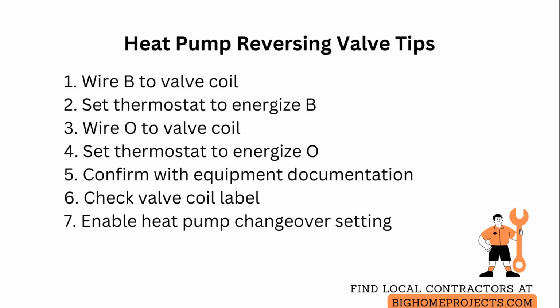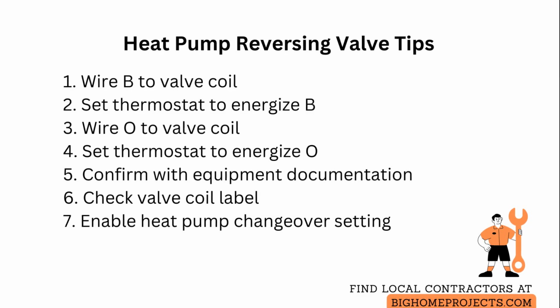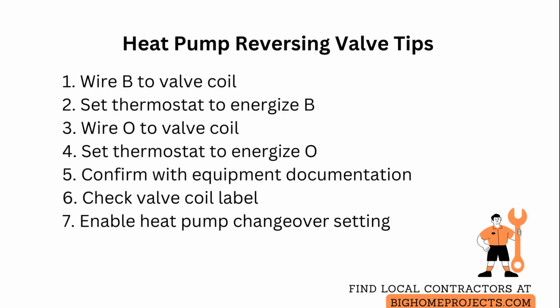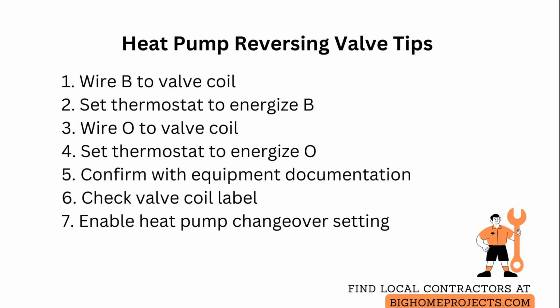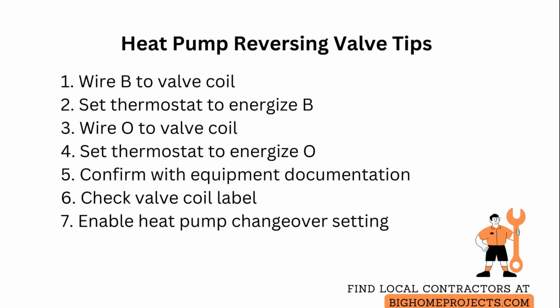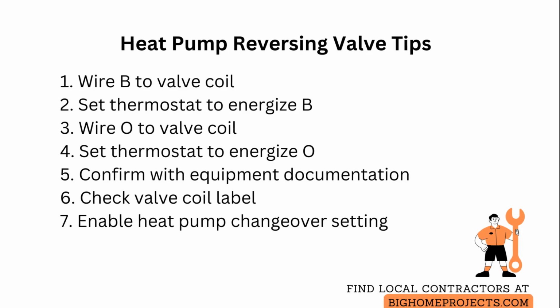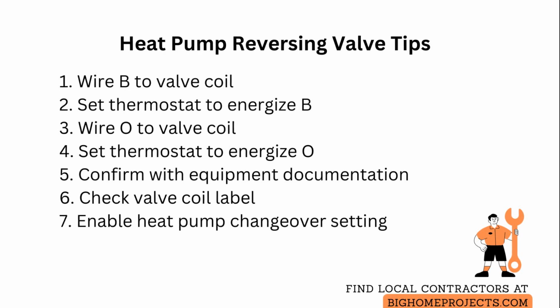Ruud and Rheem often use B to energize for heat, and most other manufacturers use O to energize for cool. Always confirm with the equipment documentation and the valve coil label, since some valves are energized in the opposite state or have built-in polarity requirements. When replacing a thermostat, enable the heat pump mode and set the changeover valve or valve orientation setting to match the terminal being used so the system does not run in the wrong mode.